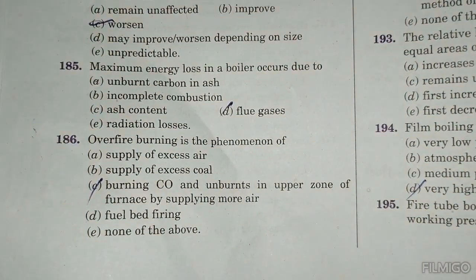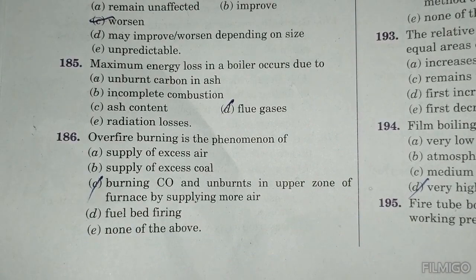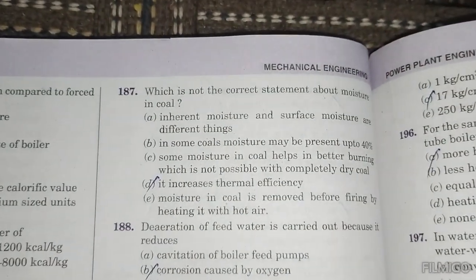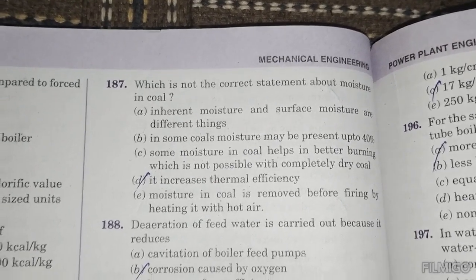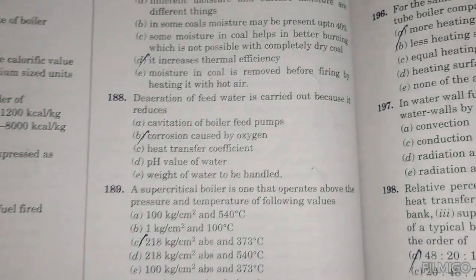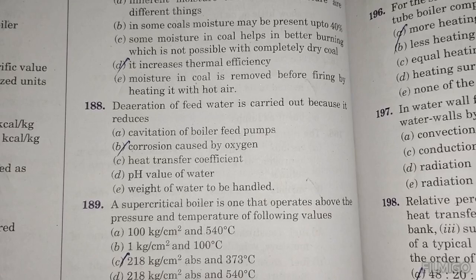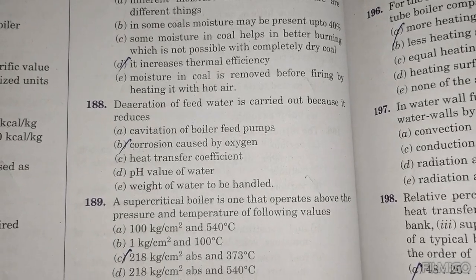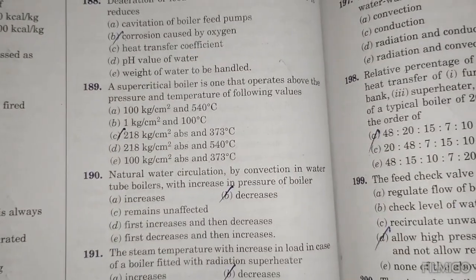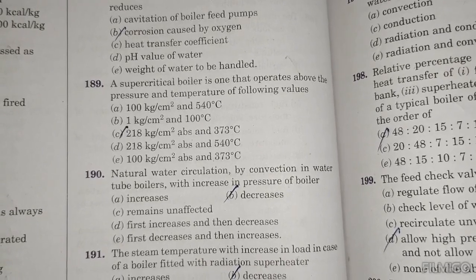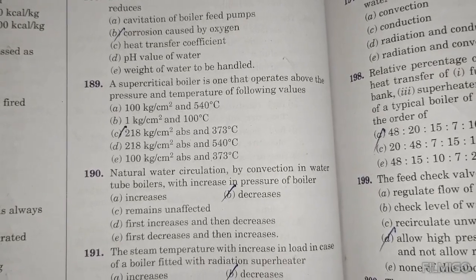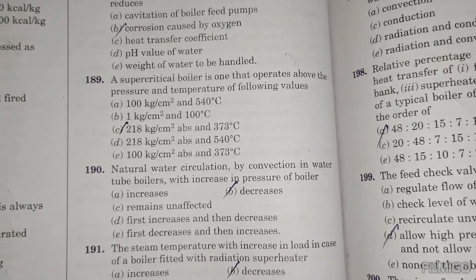Overfire burning is the phenomenon of burning CO and unburnts in the upper zone of the furnace by supplying more air. Which is not a correct statement about moisture in coal? It increases thermal efficiency. Deaeration of feed water is carried out because it reduces corrosion caused by oxygen. A supercritical boiler is one that operates above the pressure and temperature of 218 kg/cm² and 373 degrees.